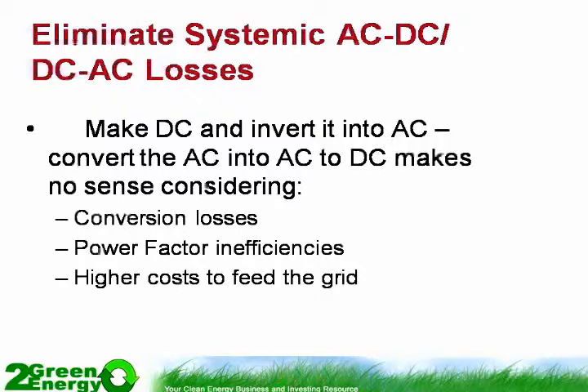On the flip side of that coin is total harmonic distortion, which causes resistance in the transmission lines, so utilities have to opt for larger wires to accommodate bad harmonics. When you have good power factor, you also have good harmonics, so the utilities are very much in favor of good harmonics.